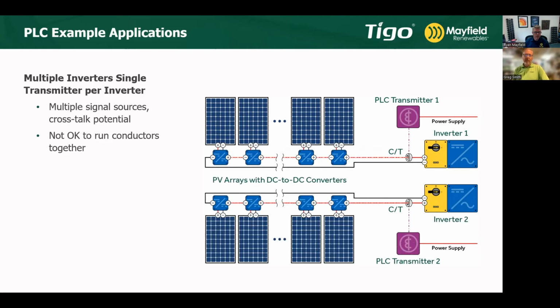So the idea here is, if you have inverter 1, 2, however many, 20, 25, you have that many transmitters. By keeping the conductors, raceways, and distance separated from each other, you won't have crosstalk issues because they're physically far enough apart. 8 inches, is that right, Greg? For us, it's 8 inches.